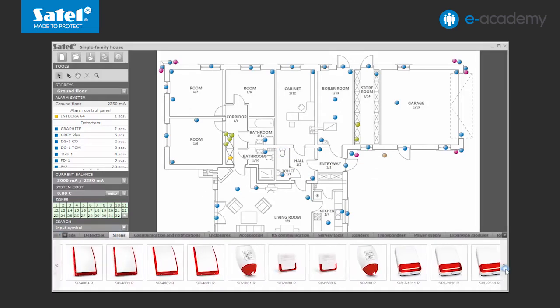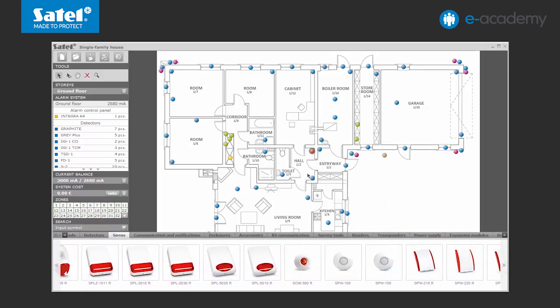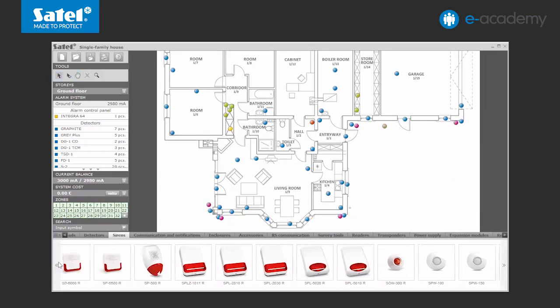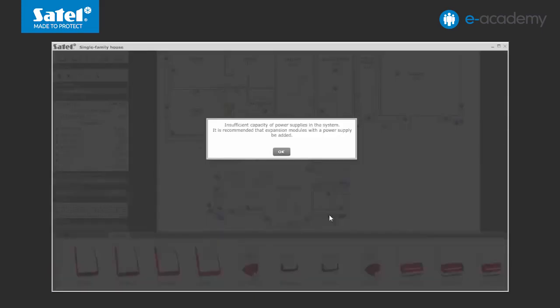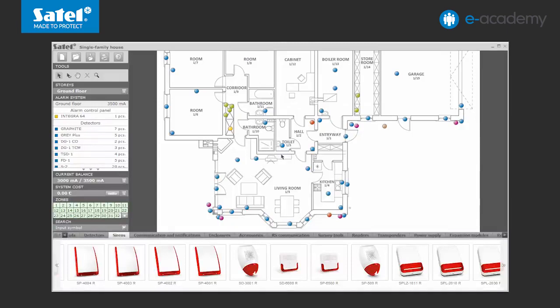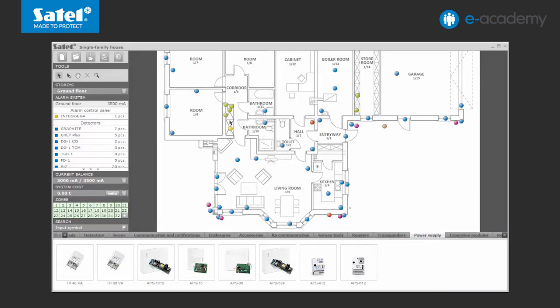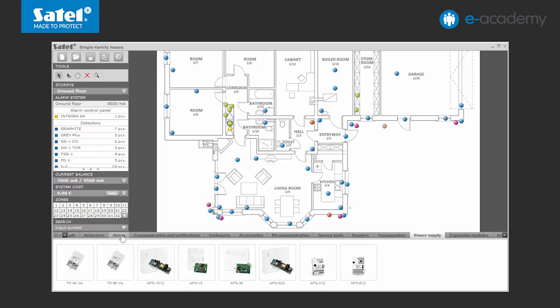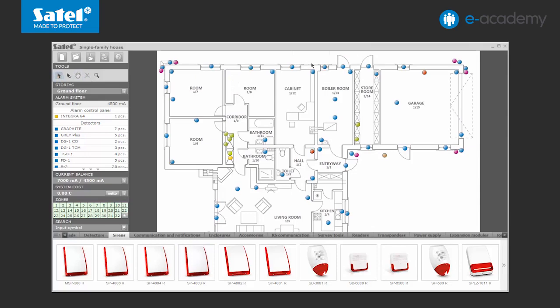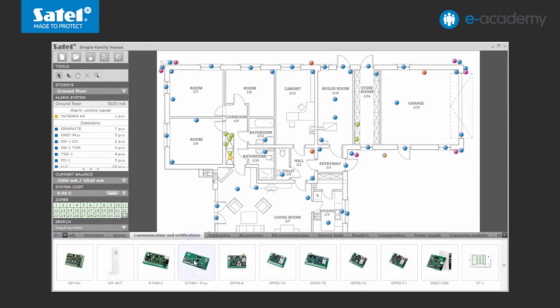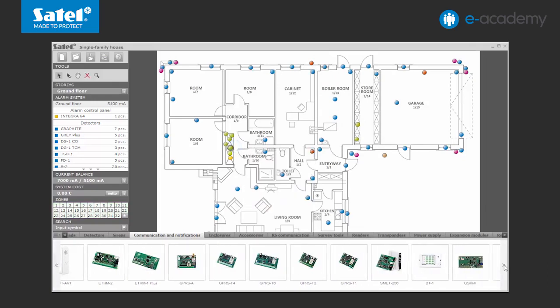Then add sirens to the system: the SPW-150 and SPW-220R indoor sirens and the SP4003 outdoor siren. Important note: the CONFX configurator's special feature is constantly checking the prepared plan for correctness. The control panel power supply efficiency is exceeded, so there is a need to add a new power supply unit. You can choose the APS412 model. The alarm system must also include devices enabling communication and notification. In our case, these are the ETHM-1 Plus and GSM-X modules.